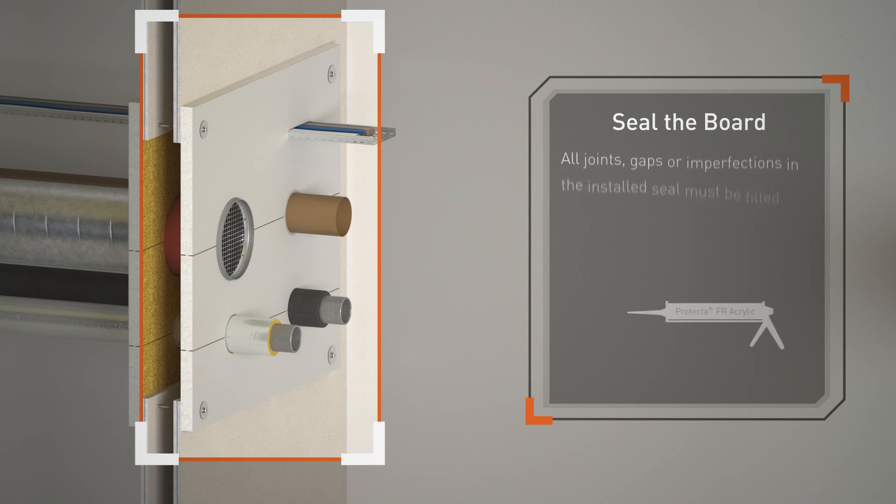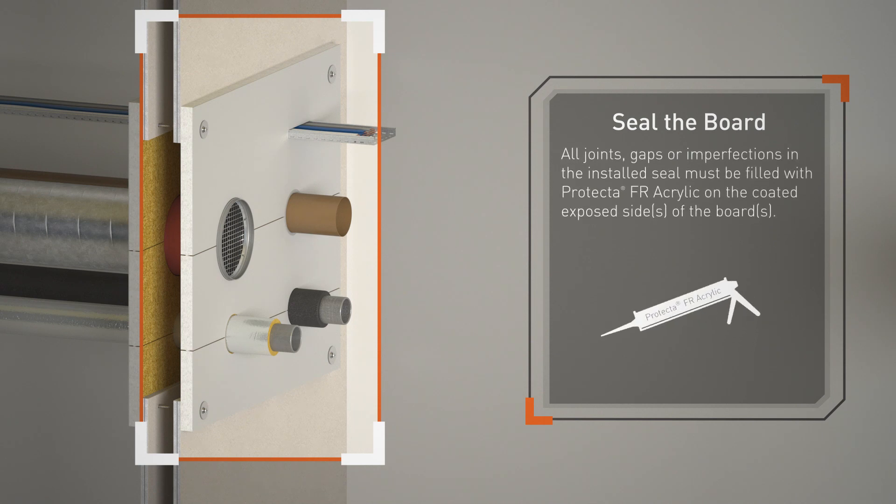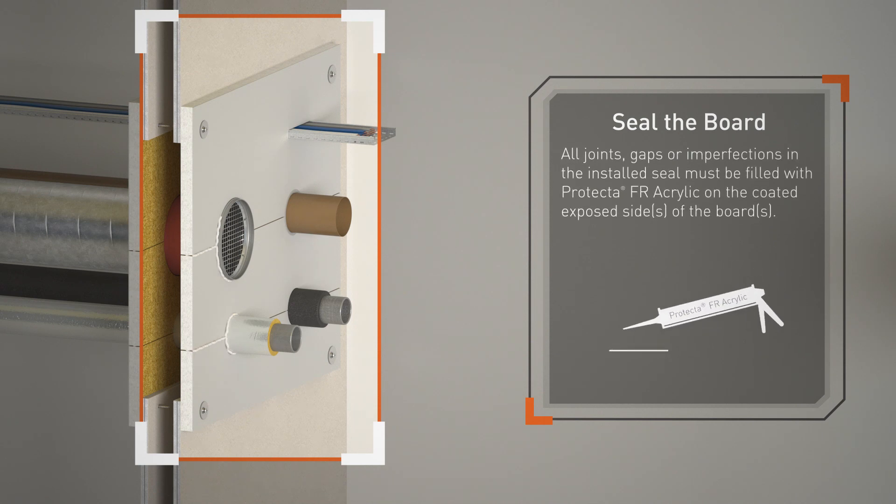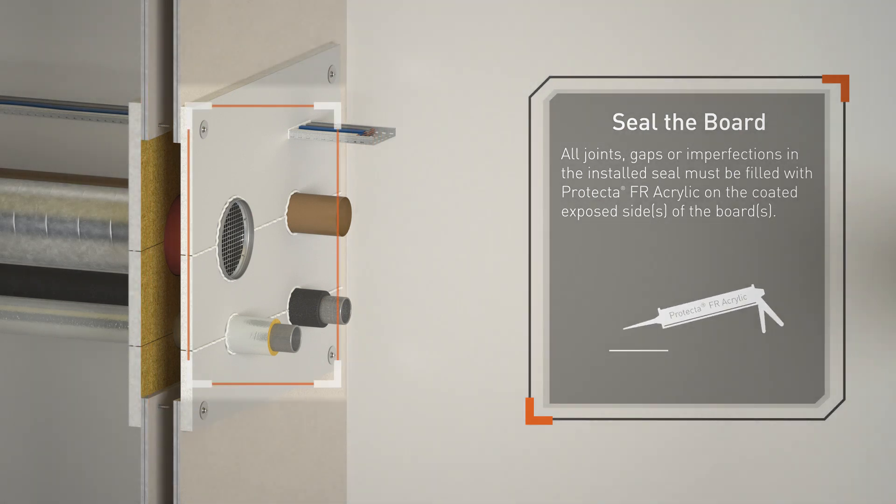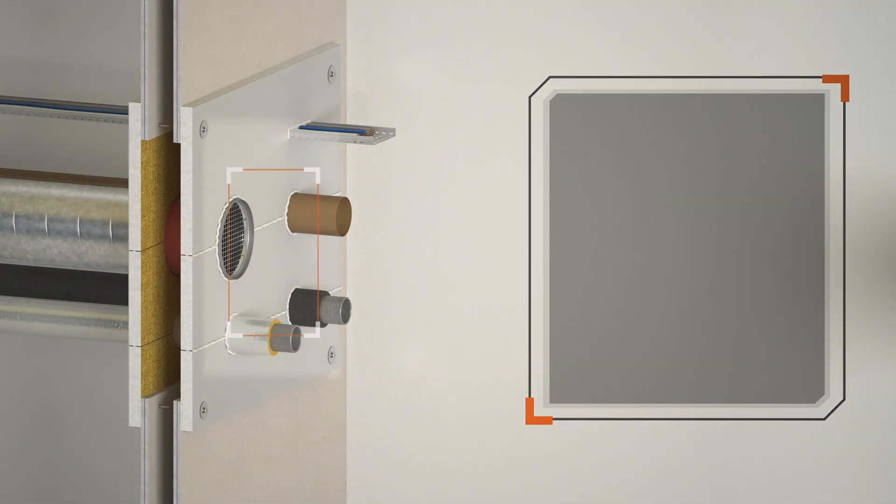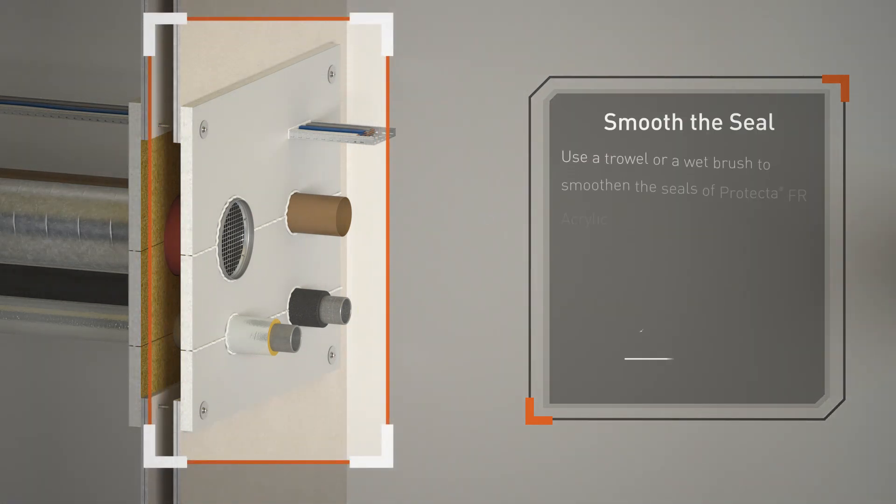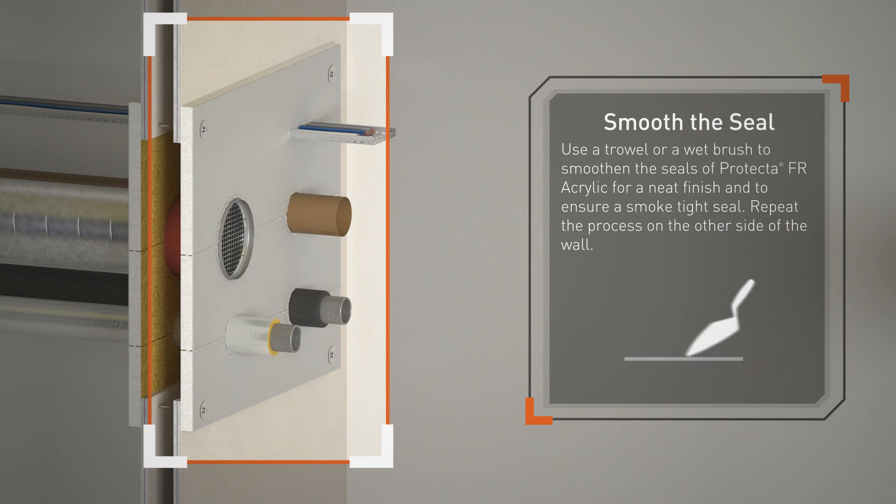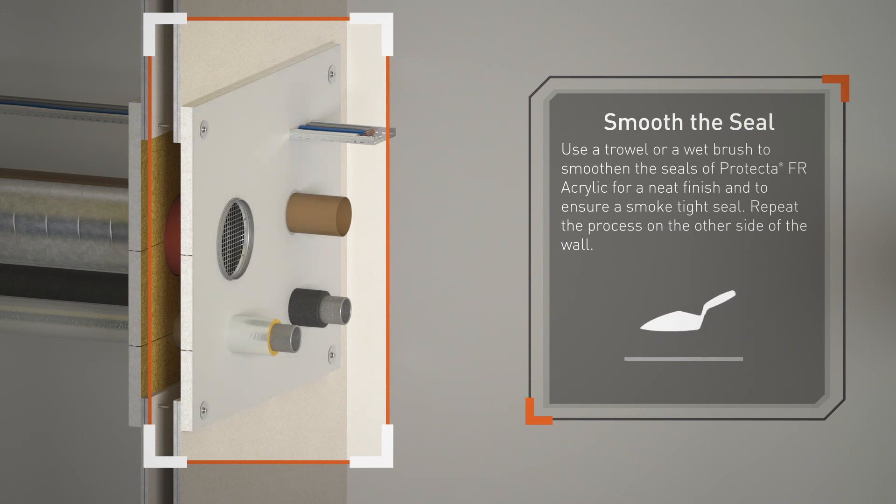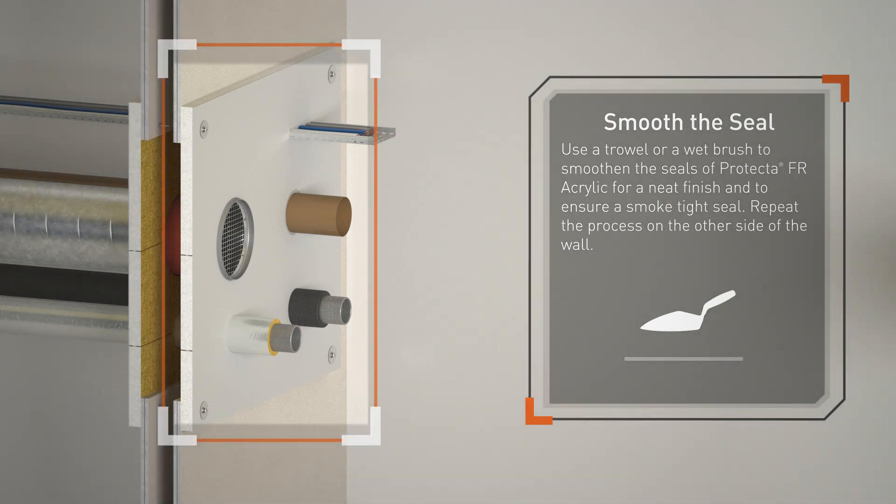All joints, gaps, or imperfections in the installed seal must be filled with Protecta FR Acrylic. On the coated exposed sides of the boards, use a trowel or wet brush to smooth the seals of Protecta FR Acrylic for a neat finish and to ensure a smoke-tight seal. Repeat the process on the other side of the wall.